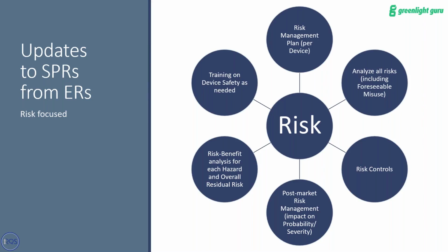Post-market risk management, so this ties back to the post-market clinical follow-up stuff and post-market surveillance, making sure that you are completing that loop of ongoing risk analysis and feedback. Risk-benefit analysis for each hazard and overall residual risk. A lot of the stuff that was in MDD regarding reducing risks as far as possible and make sure your device is state-of-the-art, those are continued and expanded on in MDR. So those didn't go away, those are still there. It's just expanding on those and making sure you add on everything else that's in MDR as well.